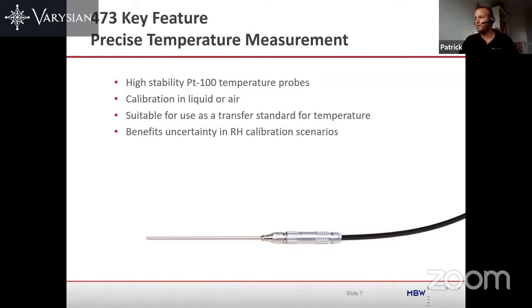Beyond humidity, we can also measure temperature. We have a highly stable PT100 temperature probe. It's calibrated in liquid or air, and it's also suitable for use as a transfer standard. That's why we say that with our 473, you can do both humidity and temperature calibration.